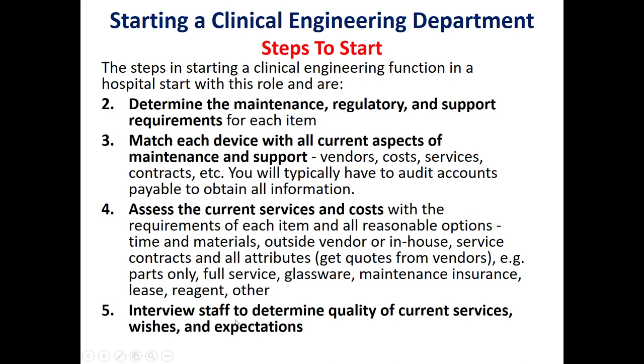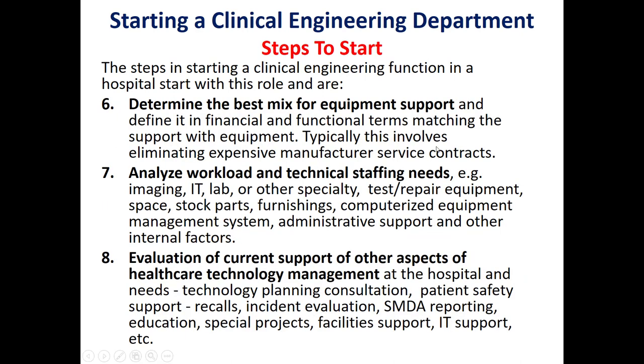We should interview the staff to determine the quality of current services — what are the expectations and wishes of the staff. Based on this feedback, we decide whether to increase in-house services or substitute with another form of support. We then determine the best mix for equipment support, making a mixture between in-house and out-house as discussed in Part 1.